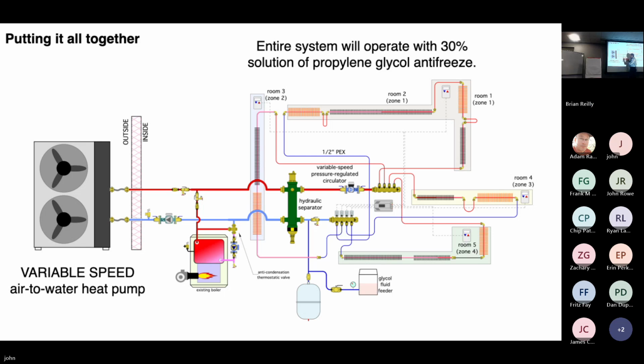Now, if that is the case, then I could tee in here and I could tee in here, and I could simply take chilled water supply and return up to a coil and an air handler. I would want to make sure though that I would have some kind of check valves in here or some kind of valving so that I don't let cool water migrate out here. Well, anybody come up with why I don't want chilled water migrating out here?